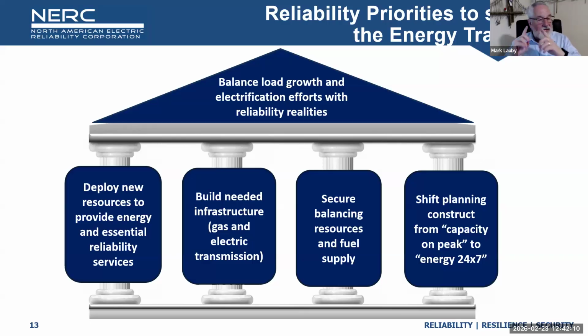And then second, how does it operate when it's under stress? For example, an event on the system, a line to ground fault. And in this case, for a large load in Dominion, 1,700 megawatts, what happened was that, as usual, you got relays that are looking at that fault and opening and closing. And there's a period of time that it does that. And basically 3 strikes and you're out. I close in 3 times and then I open up completely because it's a sustained fault.